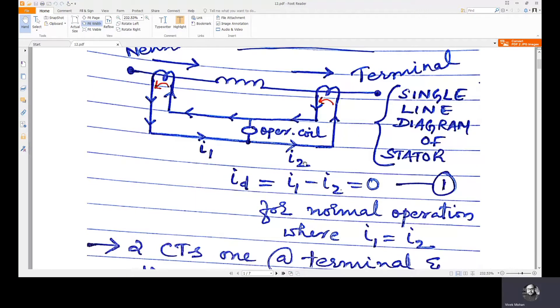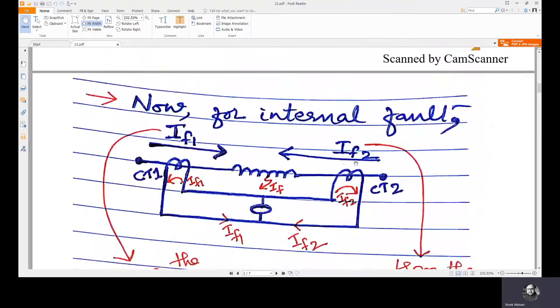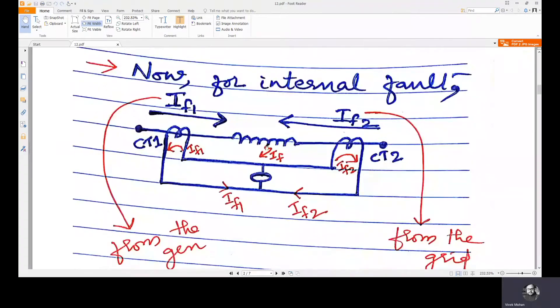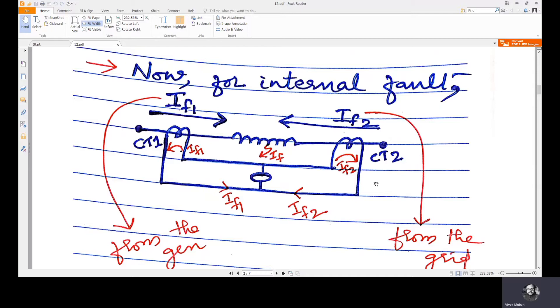For an internal fault — a fault in the stator winding — there is some fault current IF. In this case, the generator terminal is connected to the grid, so from both sides the fault current will be supplied. The current direction has reversed at the terminal side, so IF2 is reversed but IF1 follows the same direction.